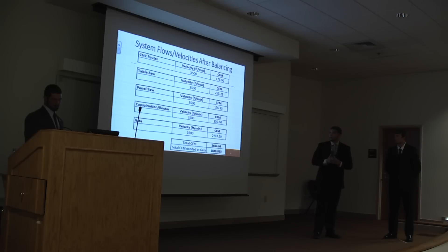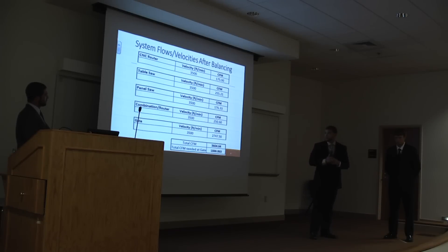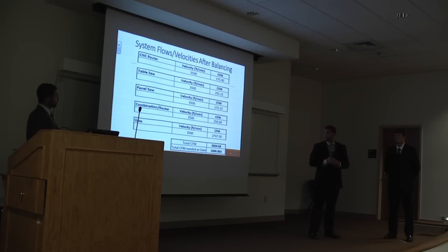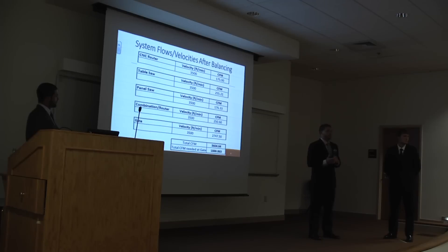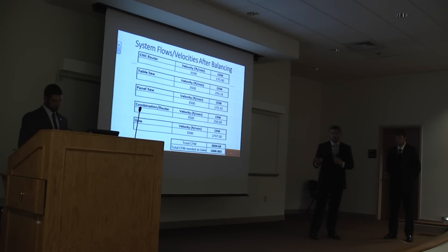At the CNC router, using the area of our designed pickup tool, you would need a flow of 175 CFM. For the table saw you need 255, the panel saw 176, and the combination router about 250. You'd also need to maintain that 3,500 feet per minute minimum velocity at the gate as well, so that when it gets to that main pipe, the dust doesn't settle. To keep the flow up there, you'd have to have approximately 2,700 CFM.